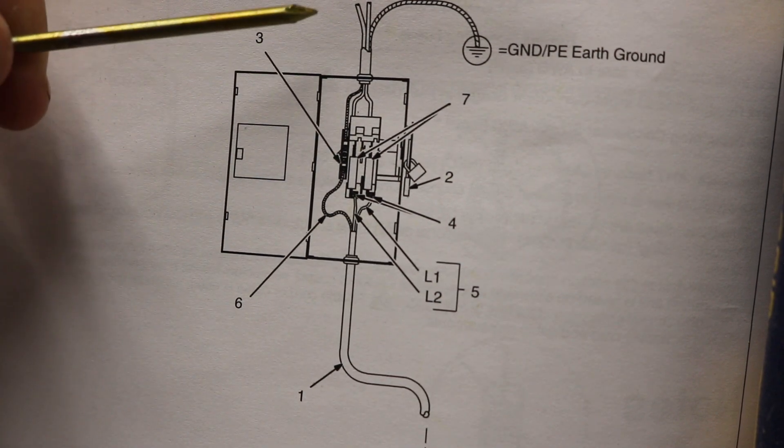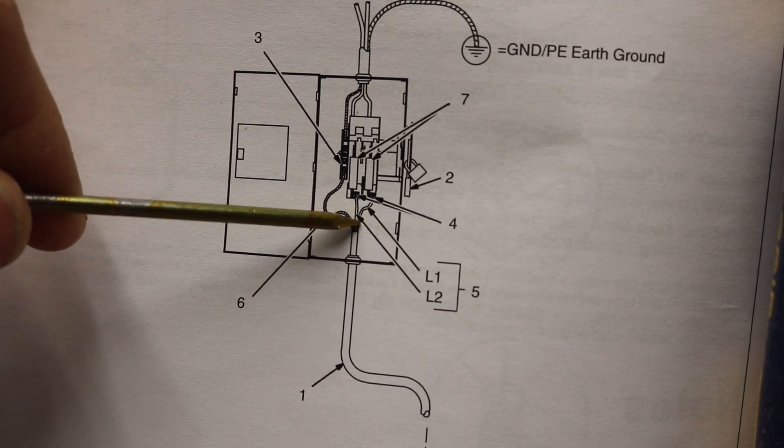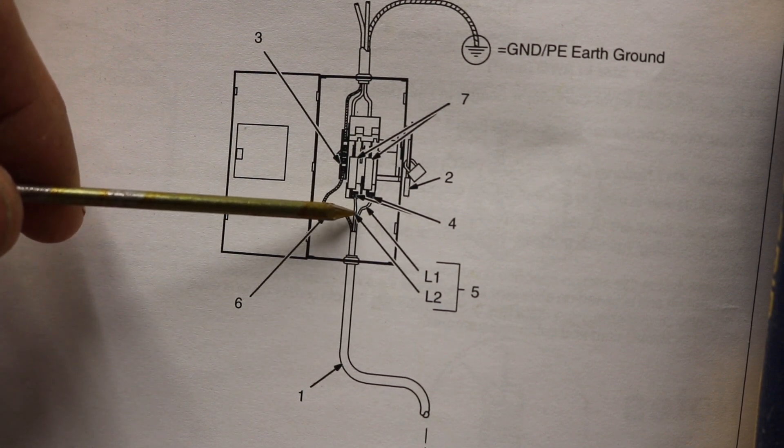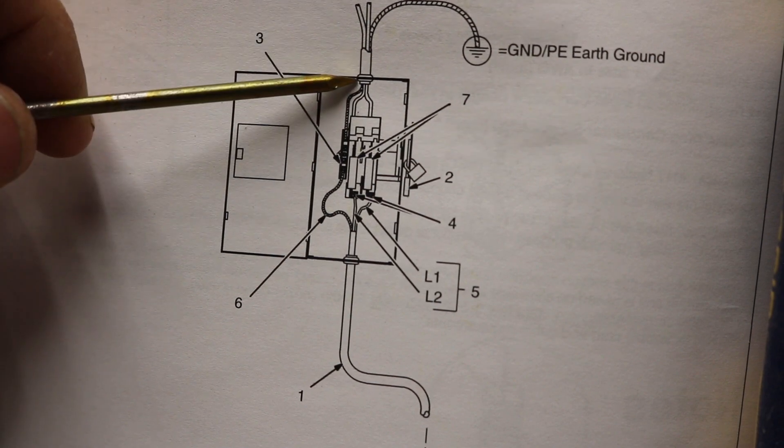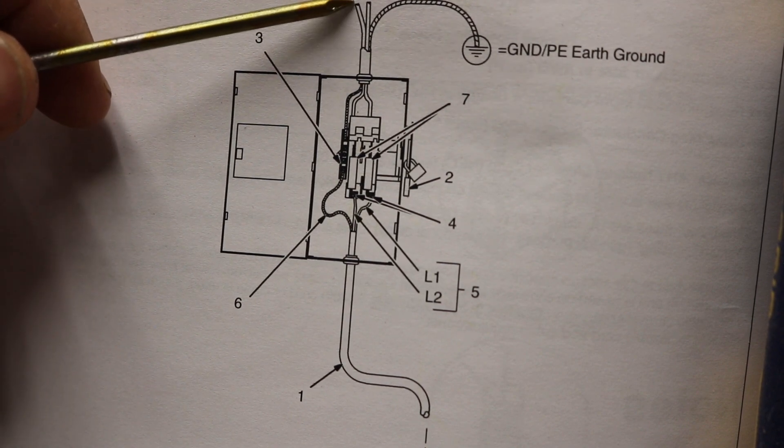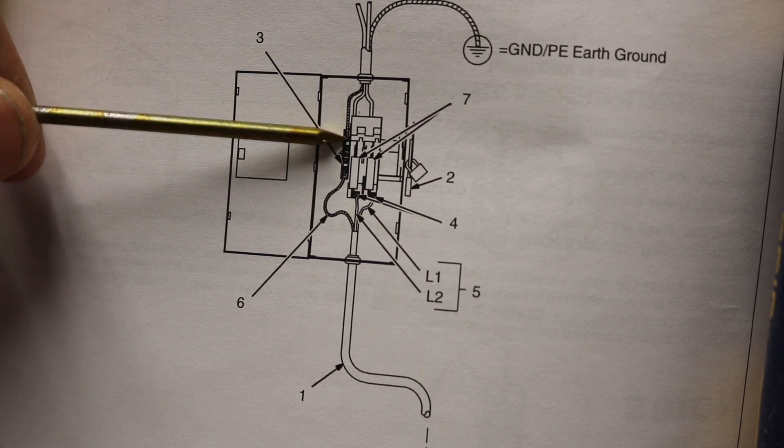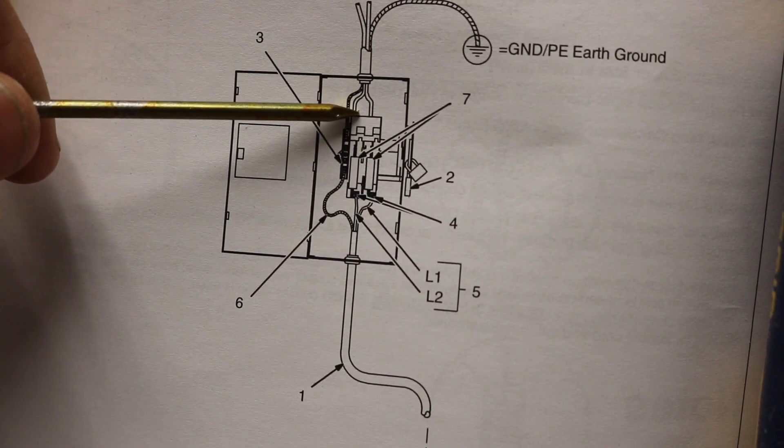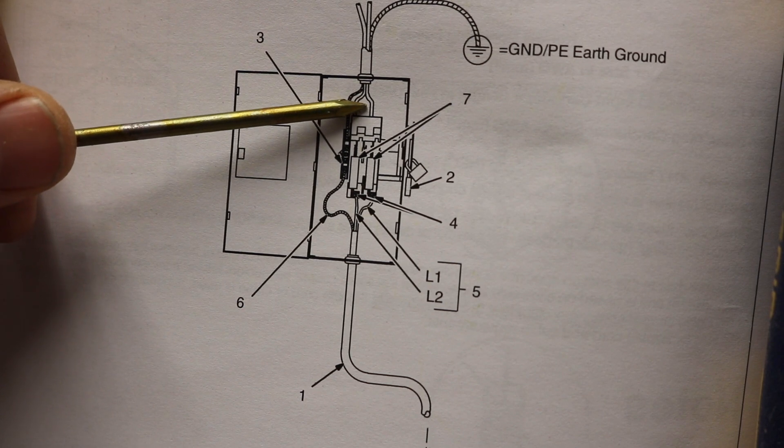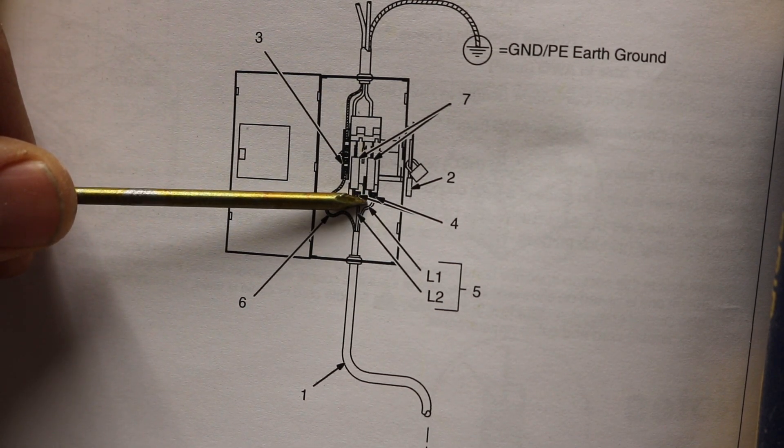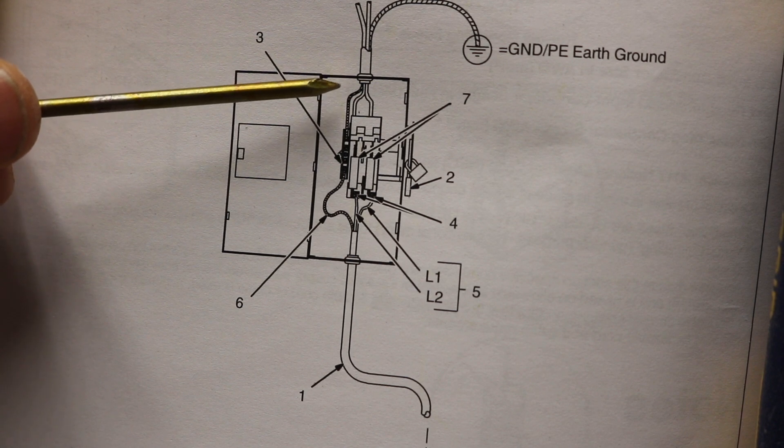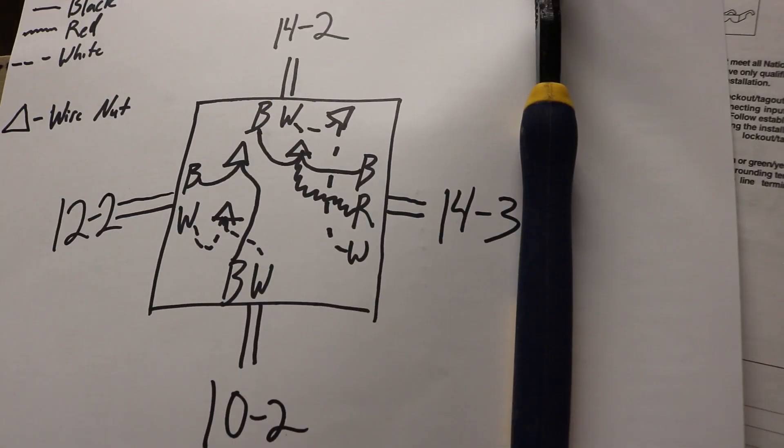When we ran this, we ran two hots. This had a black and a white because it's just SO cord. So that could confuse people because you think you just need a hot, a neutral, and a ground coming from the panel. But no, this L1 and L2 are two hots. So we ran a black and a red from the panel and then a green wire as your ground, and we hooked it up to a disconnect. The black went to the black wire on the SO cord, and then the red wire from the panel went to the white wire on your SO cord. So just know that colors don't always mean that it's a hot and a neutral.